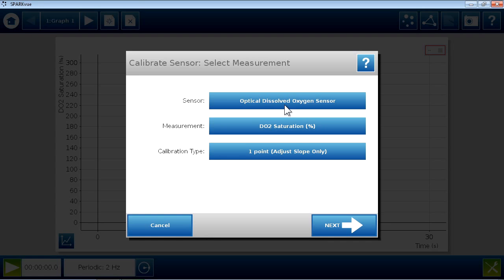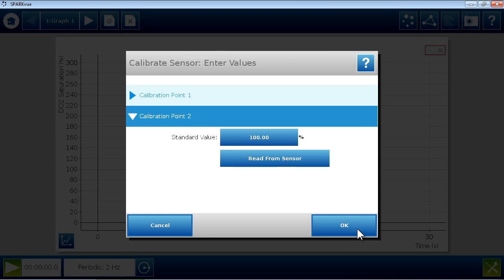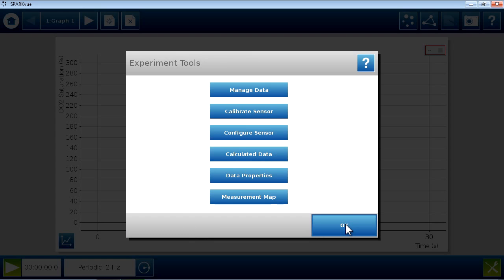Make sure the optical dissolved oxygen sensor and percent saturation measurement are selected. Then select Read from Sensor. The sensor is now calibrated, and after exiting this menu, we can proceed with the experiment.